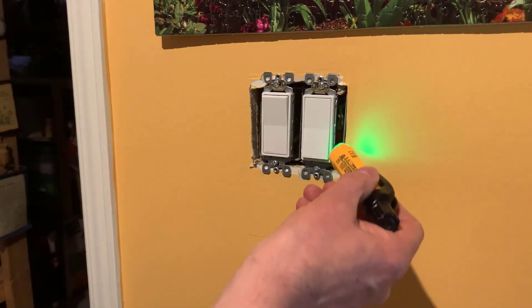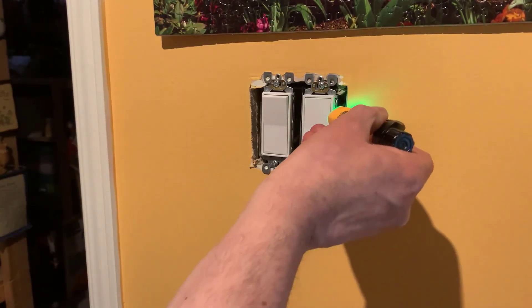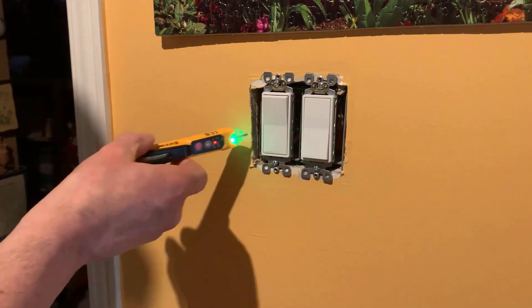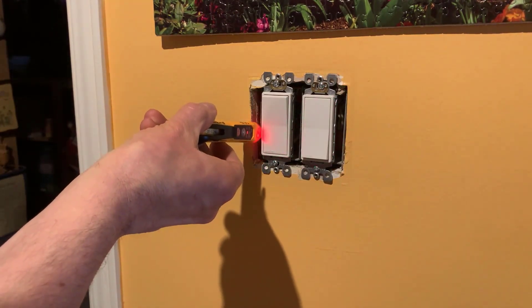The third mistake comes when you're working in a multi-gang box that has more than one switch. You've turned the breaker off for the circuit you're going to work on, that's great. But many times there are different circuits coming into that multi-gang box, one circuit for each of those switches. You need to make sure you test every wire in that box to make sure it's off, or else you could end up shorting something or touching a live wire. Use a non-contact voltage tester to make sure you test every wire in the box before you start working on the switch you're going to replace.